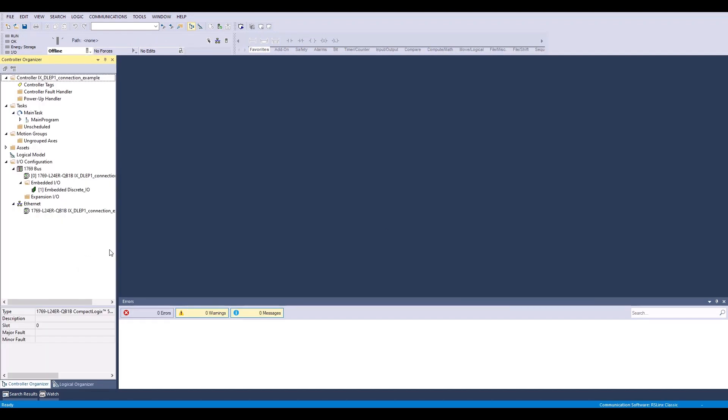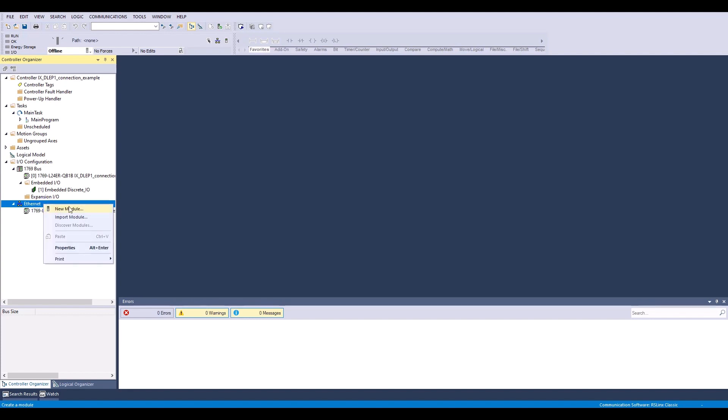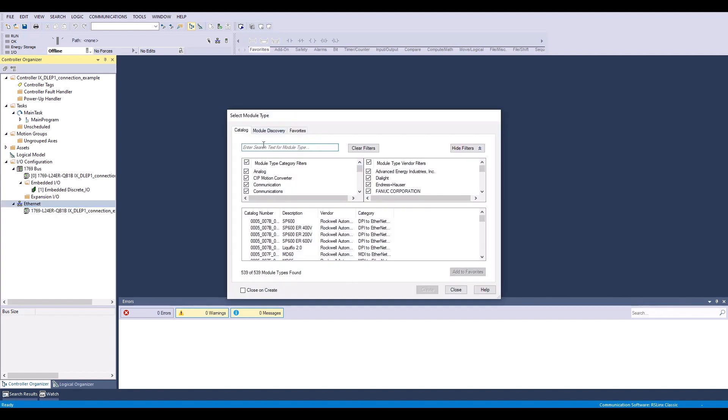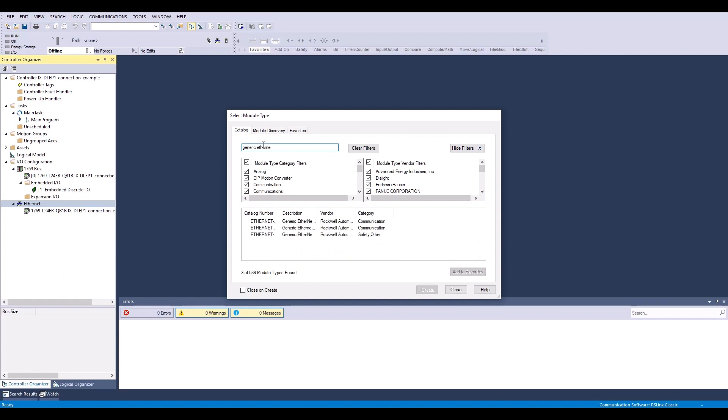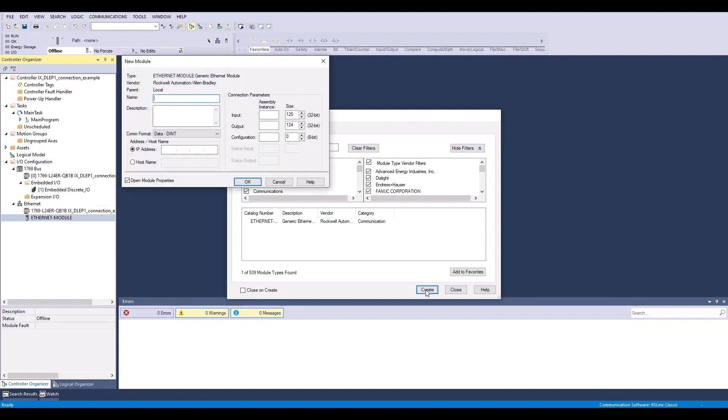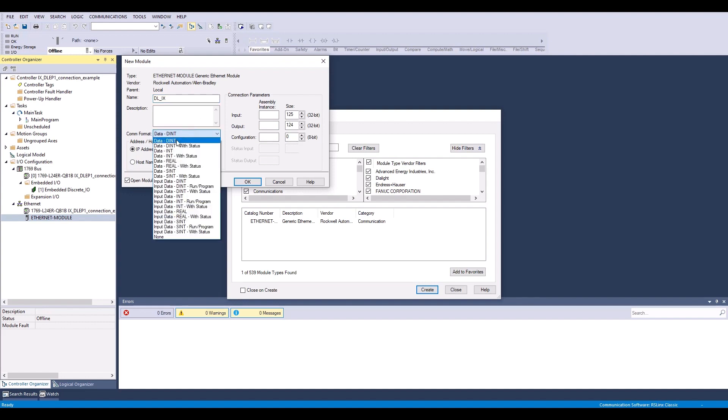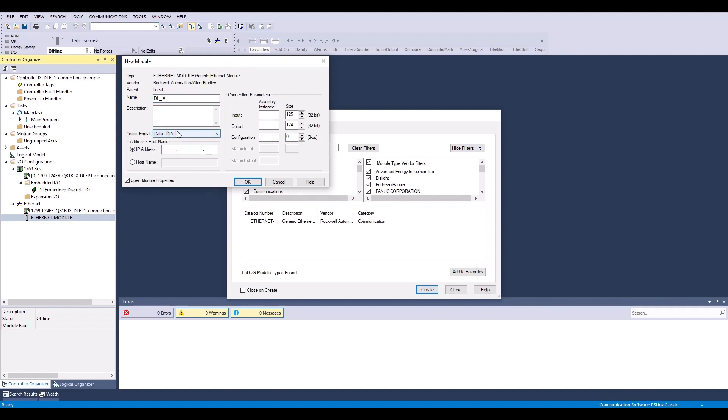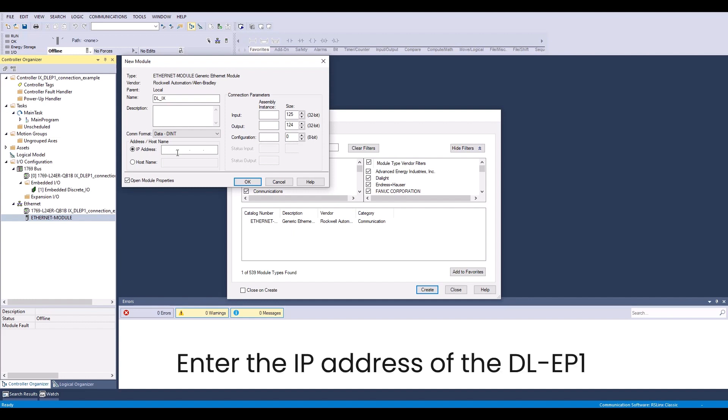The first thing we're going to do in the PLC software is right click on my Ethernet and select New Module. And I'm going to search for a generic Ethernet module. Select it here and hit Create. So I'm going to name my module DL_Ix. The data format is going to be double integer. And the IP address is going to be the IP address of my DLEP1, since that is what is communicating with the PLC. So that's going to be 172.19.102.171.